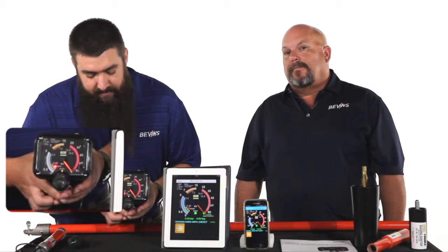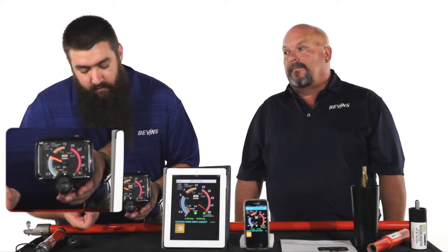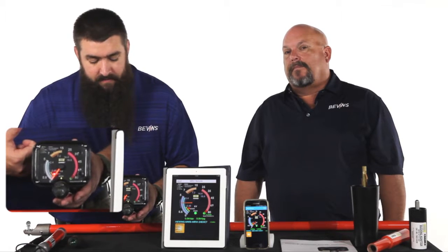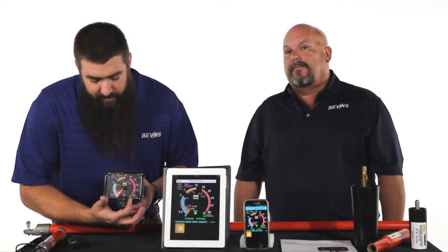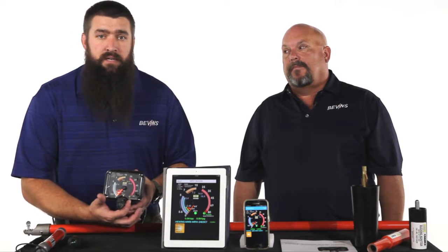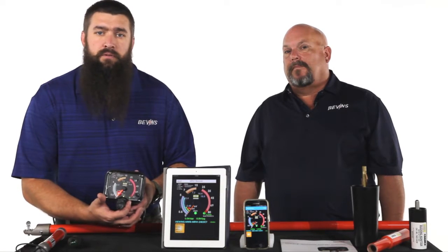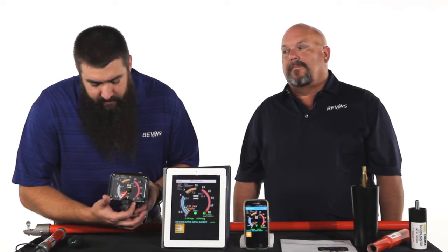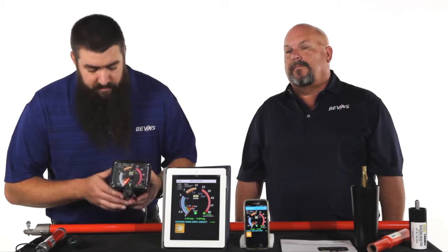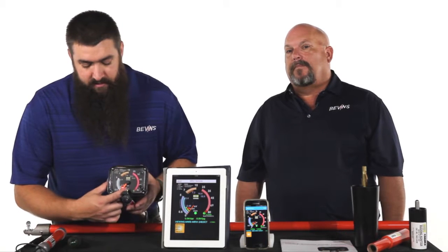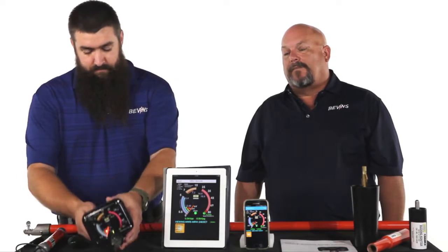What's happening is the needle pointer is running all the way up to full scale deflection to make sure it's not mechanically hung up, so you can see the needle is functioning as it should. At full scale, there's a battery life indication, pointing into the green or red area, which tests the AA batteries inside the unit. So if you're careful and keeping an eye on it during power up, you can check the batteries as well. Once the self-test has completed and it's in ready mode, we have the green ready LED on and the sense LED on solid, and we're ready to go to the next step.